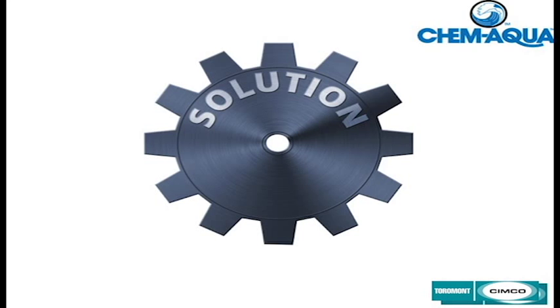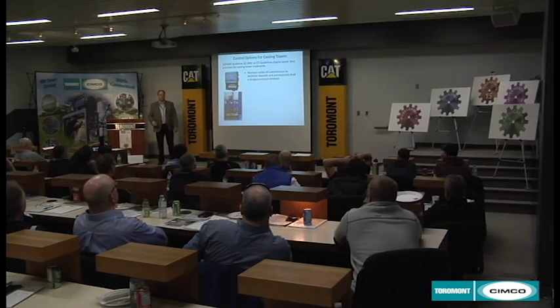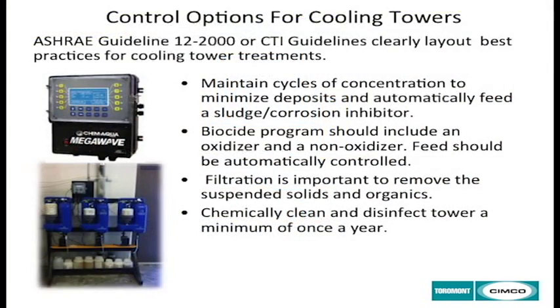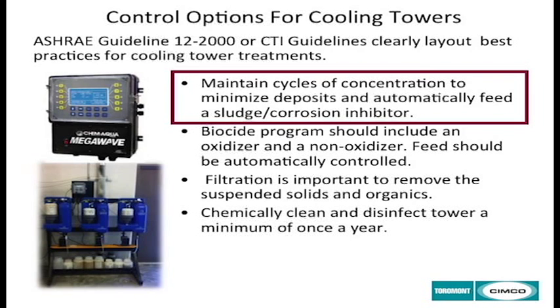Some solutions. Well, what do we have? What's in the water treatment industry? What's new with the water treatment industry? Well, there are ASHRAE guidelines and Cooling Tower Institute guidelines that clearly lay out practices for cooling tower treatment. A lot of them say maintain cycles of concentration to minimize deposits and automatically feed sludge and corrosion inhibitors.